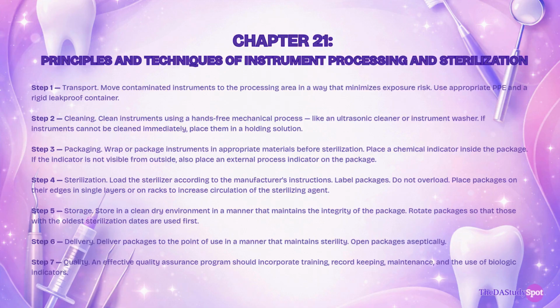Step 3, packaging. Wrap or package instruments in appropriate materials before sterilization. Place a chemical indicator inside the package. If the indicator is not visible from outside, also place an external process indicator on the package. Step 4, sterilization. Load the sterilizer according to the manufacturer's instructions. Label packages, do not overload, and place packages on their edges in single layers or on the racks to increase circulation of the sterilizing agent. Step 5, storage. Store in a clean, dry environment in a manner that maintains the integrity of the package. You want to rotate packages so that those with the oldest sterilization dates are used first.